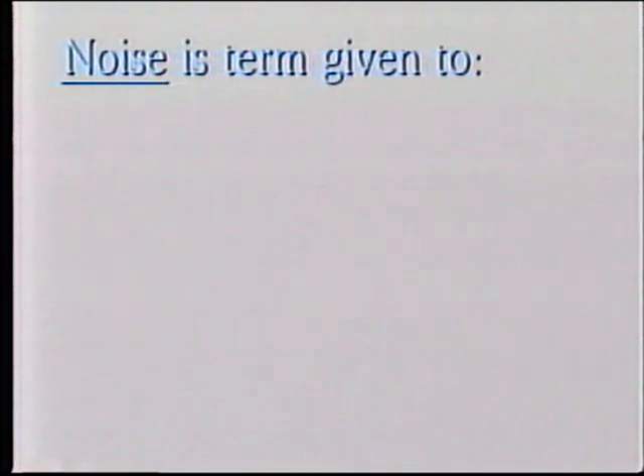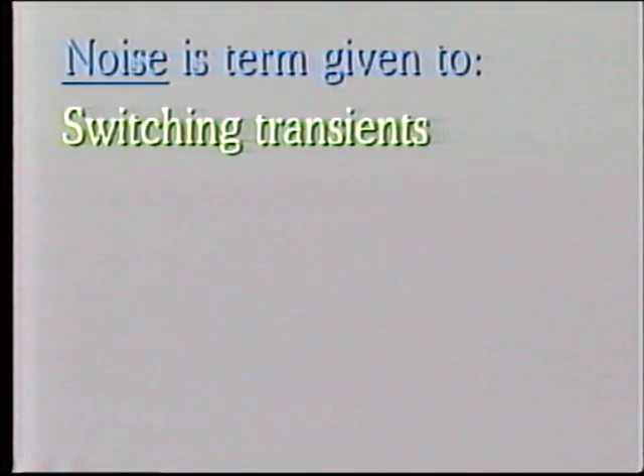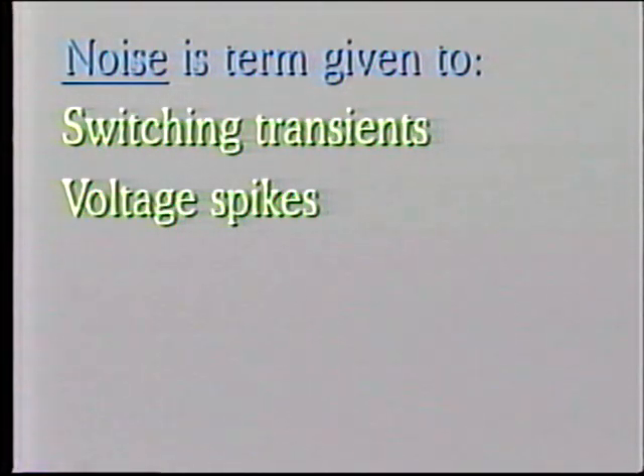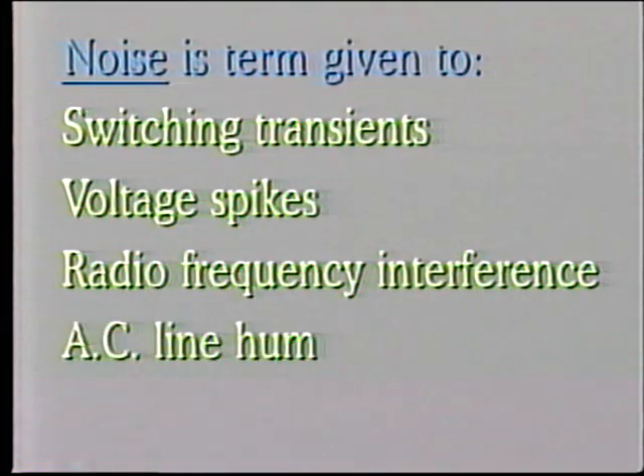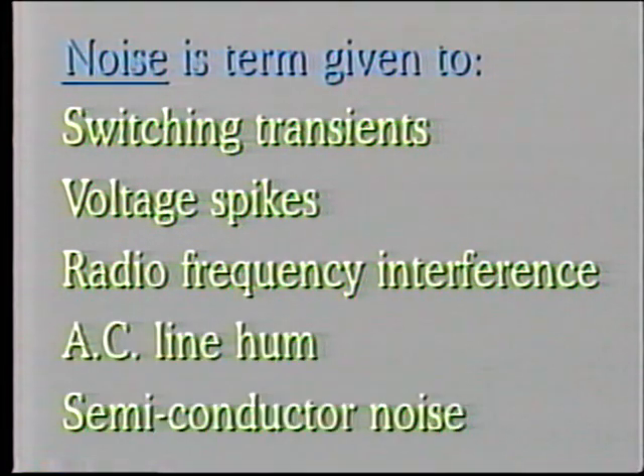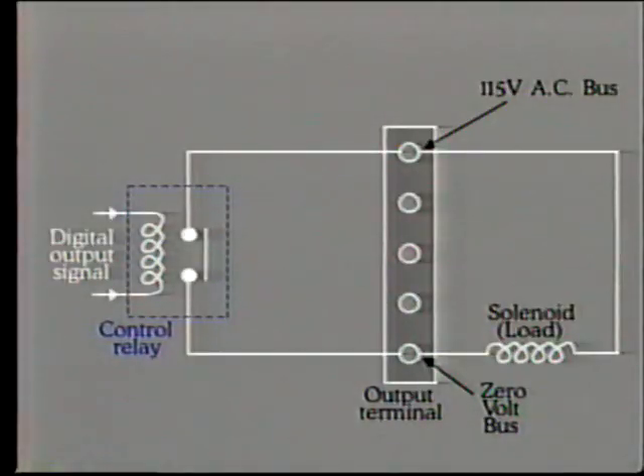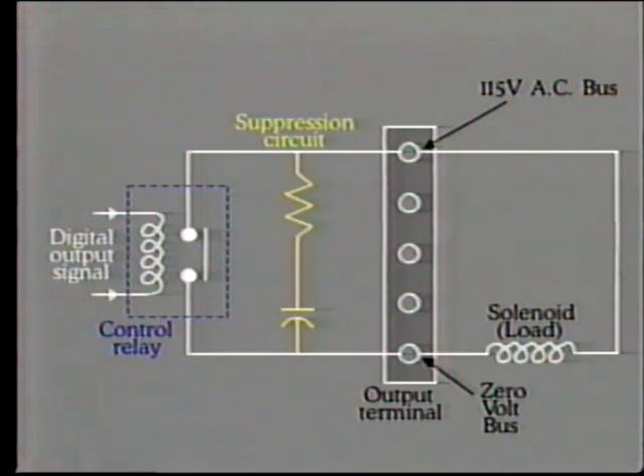We have already mentioned the need for isolating and protecting the CPU from interference due to so-called noise on the input signals and power supply. Noise is the term given to switching transients, voltage spikes, radio frequency interference, AC line hum, semiconductor noise, and so on. The effect of switching transients can be reduced by connecting a suppression circuit across relay contacts.